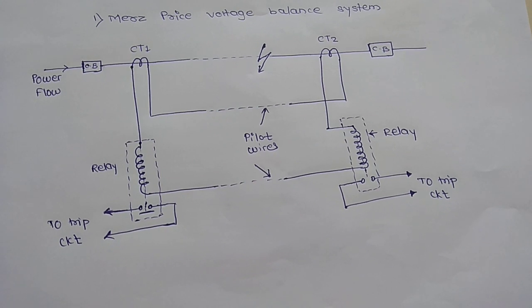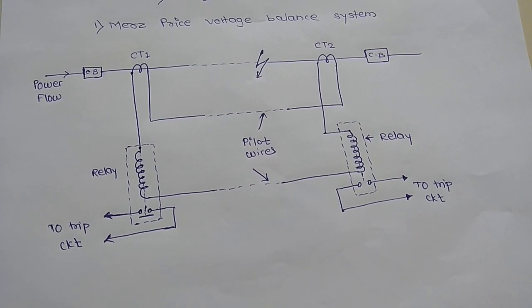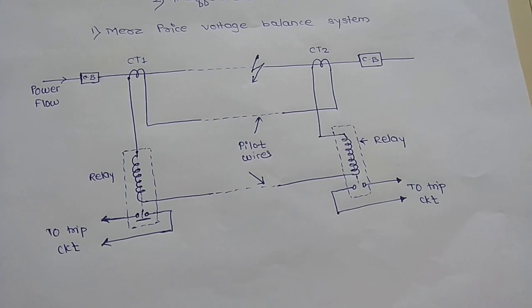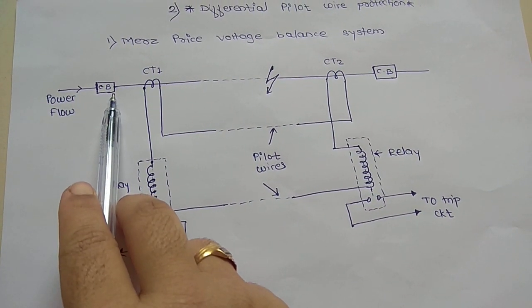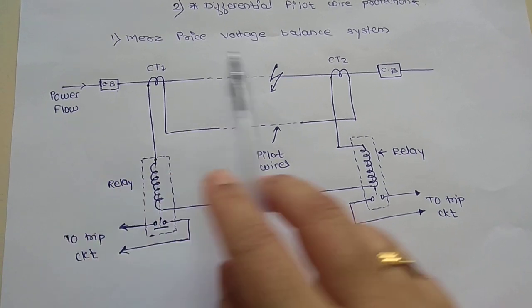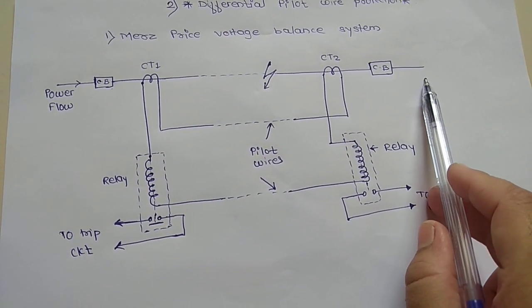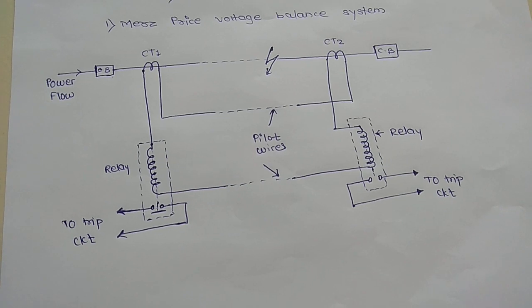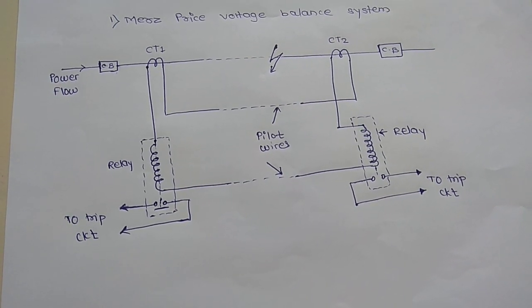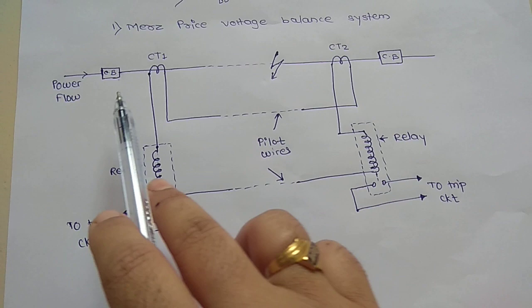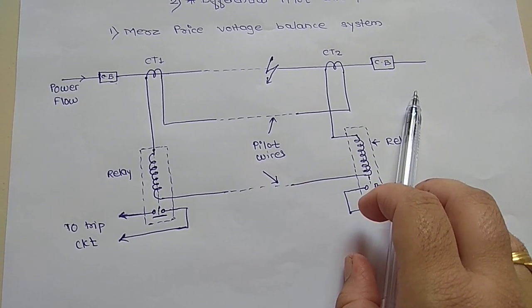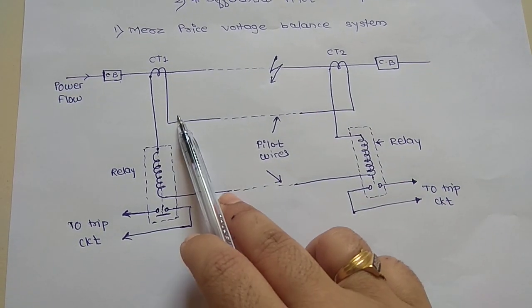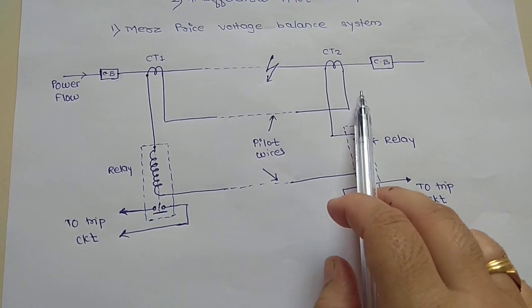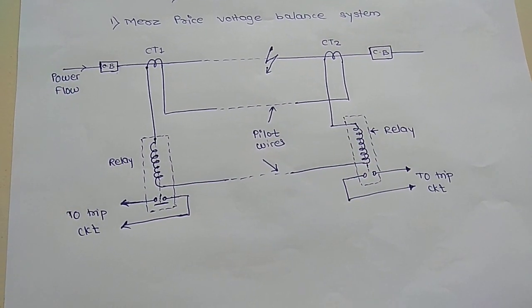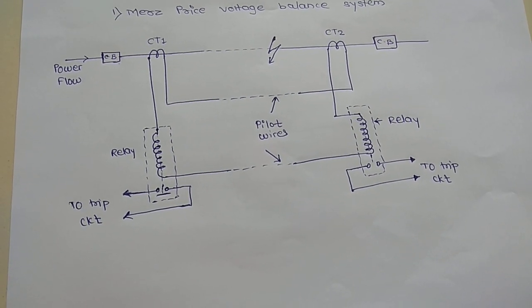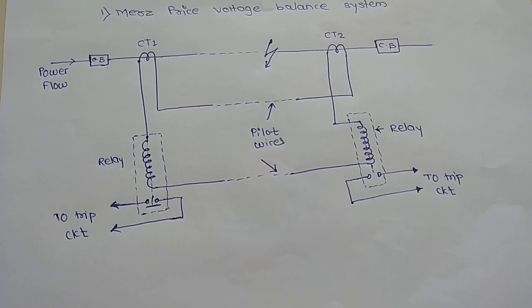During this normal operating condition, that is a healthy condition, current entering the line at one end is equal to current leaving from the other end. Therefore equal and opposite voltages are induced in the secondary of the CT. As a result, no current flows through the relay coil because this is a healthy condition.